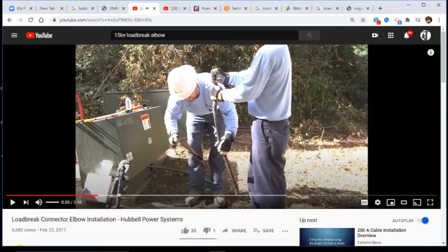Okay, so the common error that people make here as far as getting ready to make their elbow termination is they think the end of the wire, as far as the measurement, is what goes on the module that we worked out there at the field. That's where I need to install my elbows, right at the end of the wire. You have to give yourself sufficient ground, and you all saw the grounds coming off the elbows, to reach the ground plus the elbow. So make sure that you take off enough outer jacket, and you're usually going to use just a skinny knife and a strand of the wire to peel it off. Make sure you have sufficient ground to reach the ground plus the elbow install. The elbow install is going to be way down here, and he's got enough ground wire to reach down to the ground.